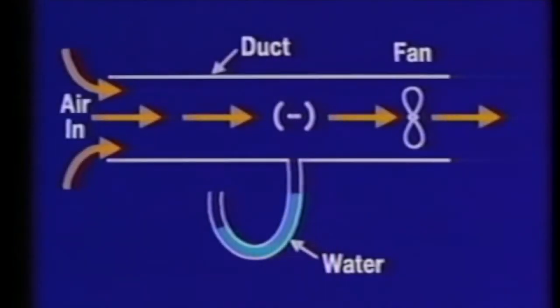Air is pressurized by gravity, the barometric pressure. At sea level, the barometric pressure is about 29.9 inches of mercury as measured with a barometer. The barometric pressure is also called the absolute static pressure. Air starts moving because there is a difference in pressure between 2 points. Air moves from an area of higher pressure to an area of lower pressure.